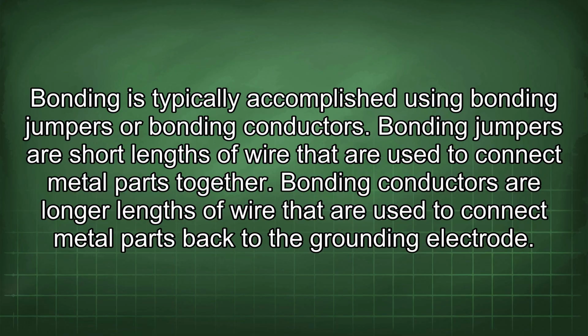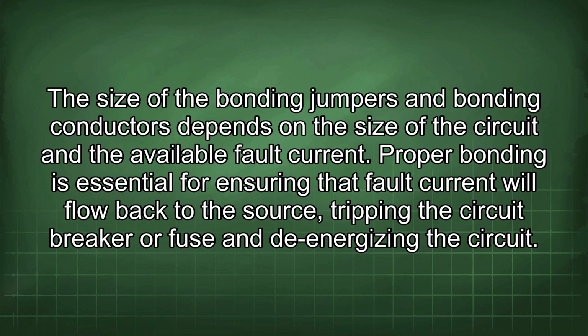Bonding jumpers are short lengths of wire that are used to connect metal parts together. Bonding conductors are longer lengths of wire that are used to connect metal parts back to the grounding electrode. The size of the bonding jumpers and bonding conductors depends on the size of the circuit and the available fault current. Proper bonding is essential for ensuring that fault current will flow back to the source, tripping the circuit breaker or fuse and de-energizing the circuit.